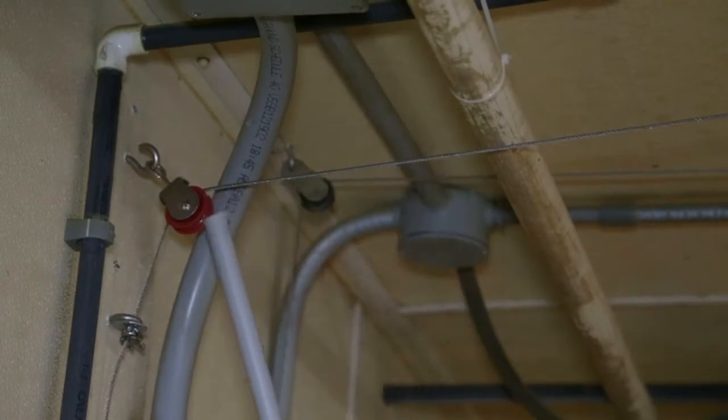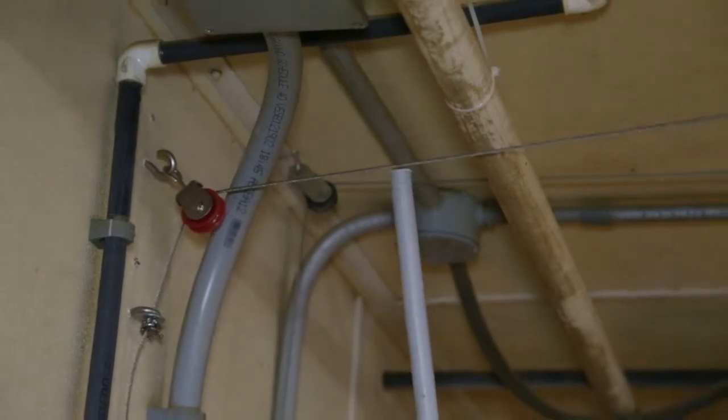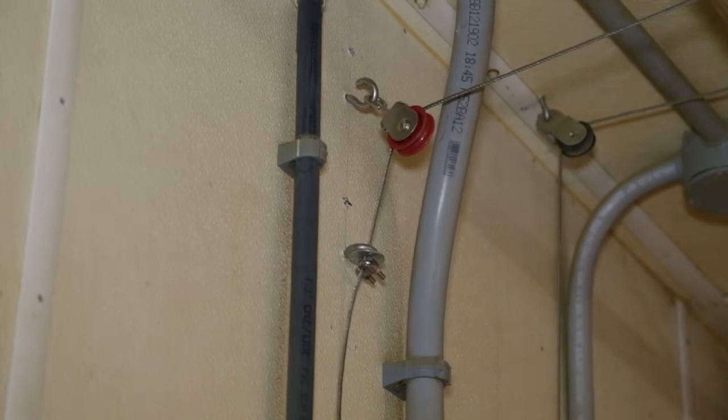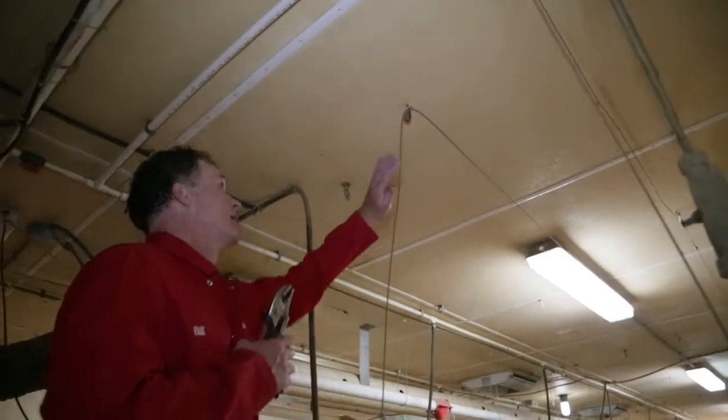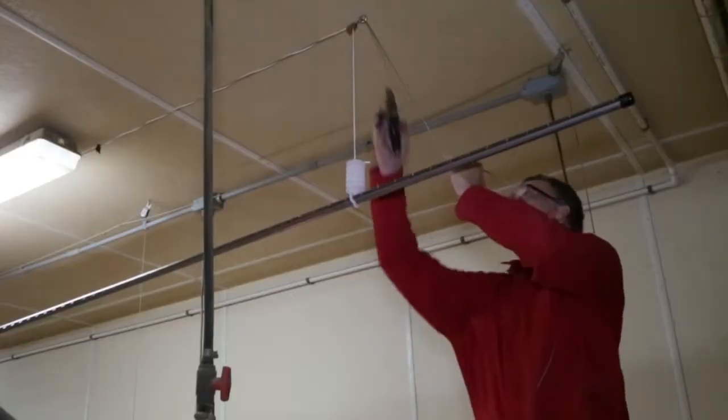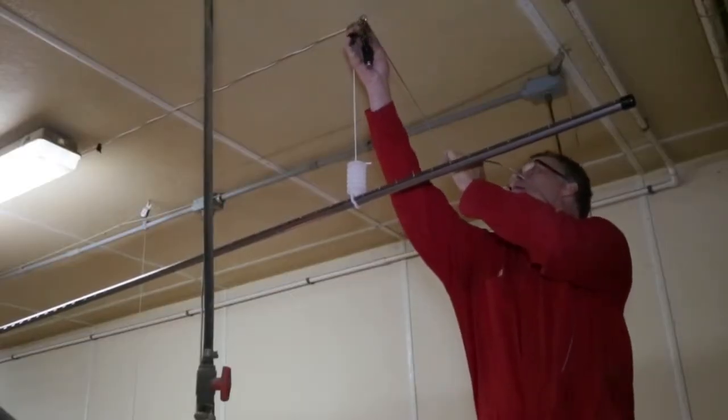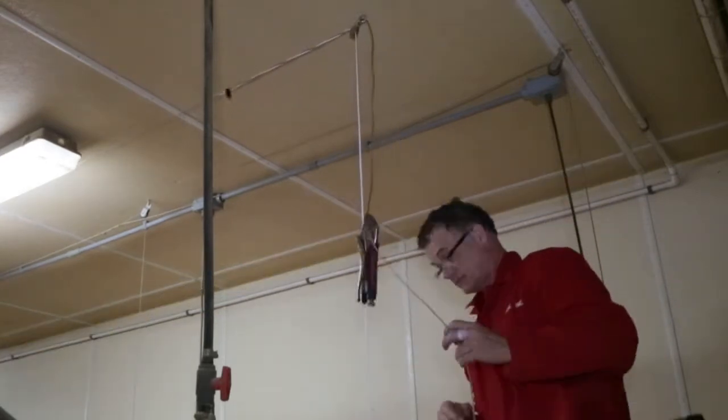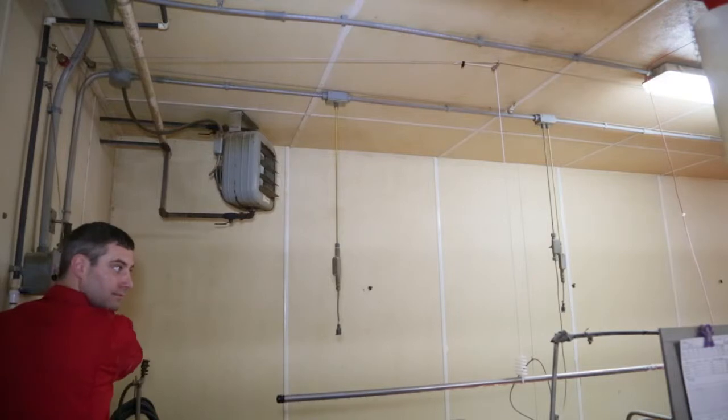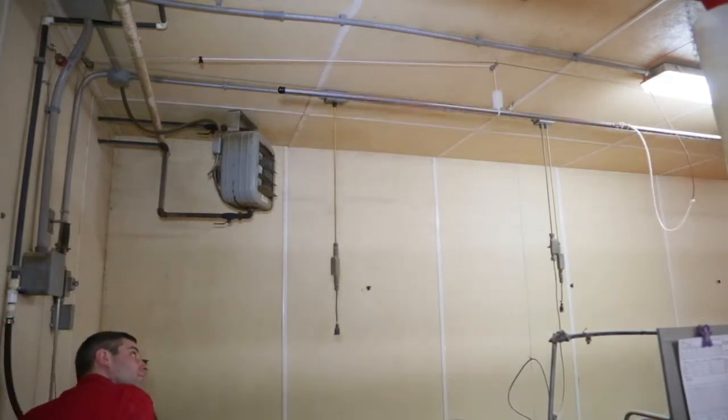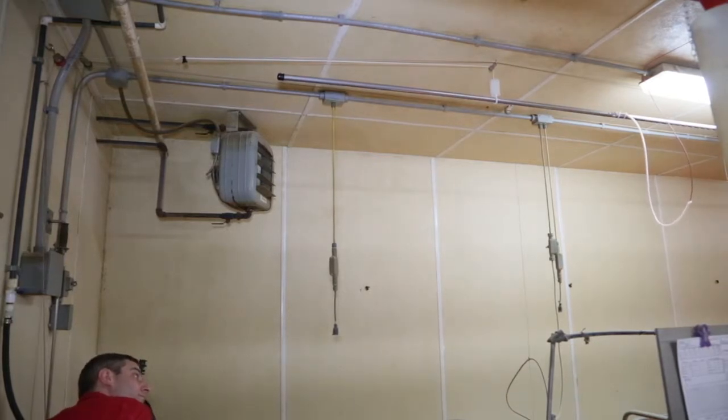There must be enough distance between the handle and the pulley to allow for maximum travel of the corona pipe runs. The winch must be able to pull the corona pipe runs all of the way up. Pull the cable through the eyes of the pulley supports. Tie or clamp the end of the cable to the last or furthest corona point support. Or attach a dead weight to remove cable sag. Allow 5 extra feet of cable. Do not allow the cable to rub on other objects. Allow enough cable movement for the corona pipe runs to travel the maximum up and down.